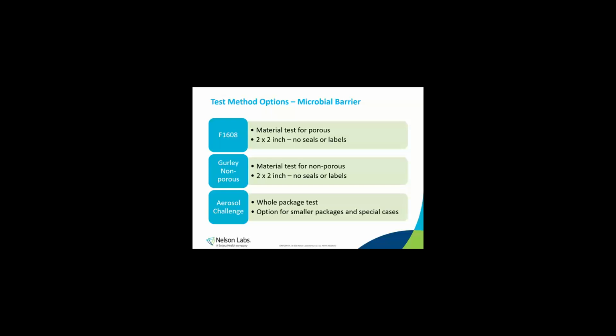The aerosol challenge is a custom test where whole packages are placed in a chamber and lightly showered with Bacillus atrophaeus spores. The packages are aseptically opened and the contents removed and checked for the presence of Bacillus using sterility test techniques. As you can imagine, it's not easy to open a package covered with an indicator organism without getting cross-contamination. And the test is dependent on the probability of the organism landing in just the right location to be detected. So there are some limitations to this test. Aerosol challenge is also a pass-fail test.